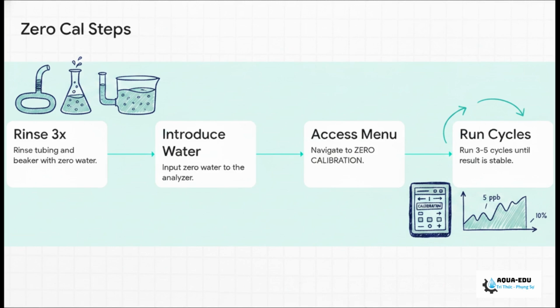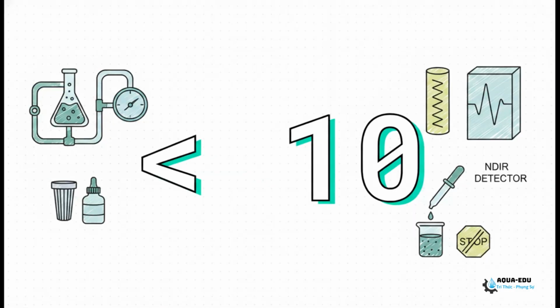What we are looking for here is stability, meaning a deviation of less than 5 ppb between runs or less than 10% of your operation range. Our target is incredibly strict, less than 10. If your zero reading isn't coming in under 10 to 20 parts per billion, you need to stop immediately. Check your zero water quality, inspect that CO2 scrubber, look for any acid reagent contamination, and check for NDIR detector drift.